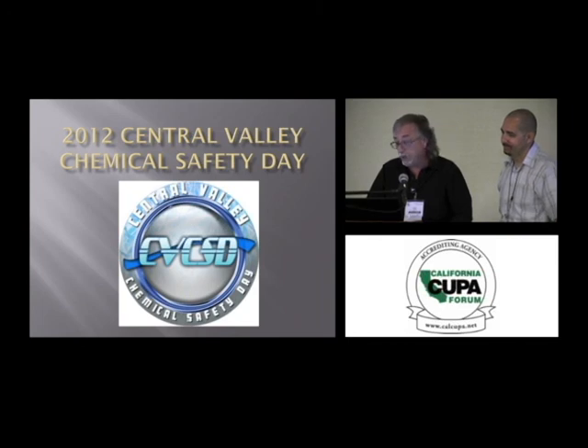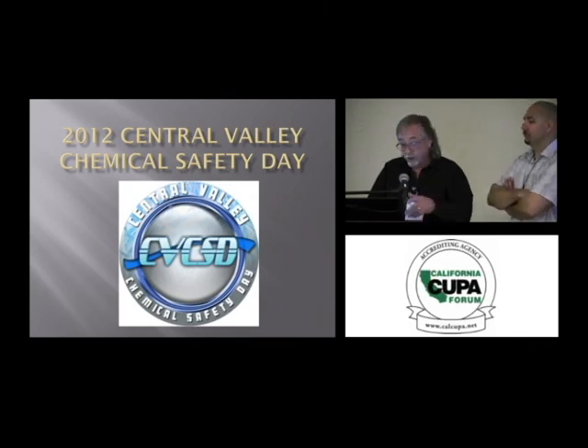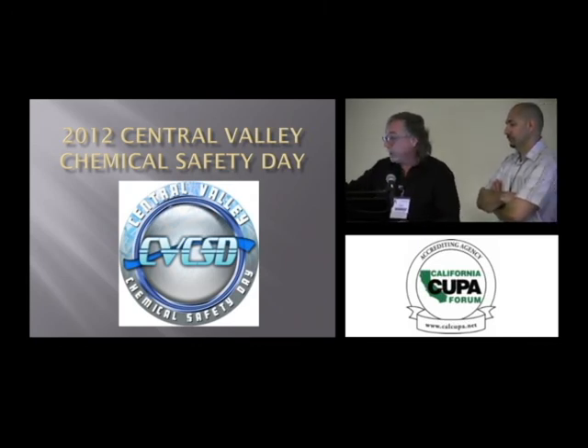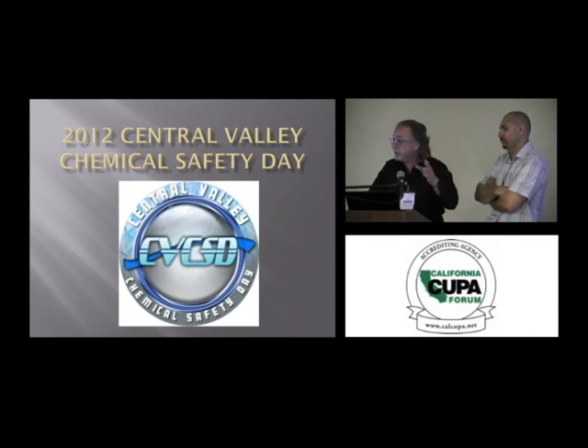The other thing is, real quickly, every piece of equipment we have out there is supposed to have a unique identifier per IIAR. So this is an oil pot. It should say oil pot number 1 or OP-1 or something. Okay? If I've got a fireman and I want to send them in there on an emergency, I want to be able to tell them what to look for. Otherwise, I'm going to have to tell them, that little blue thing. Much better if you've got an identifier on it. I'll let you take a couple.